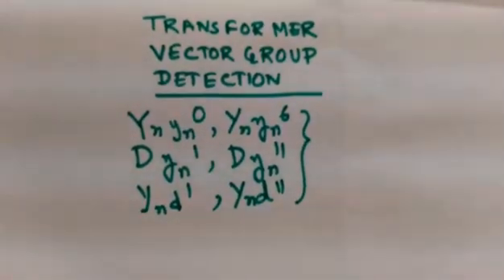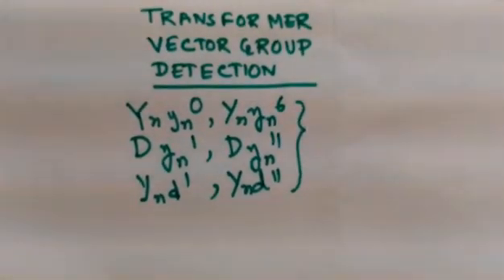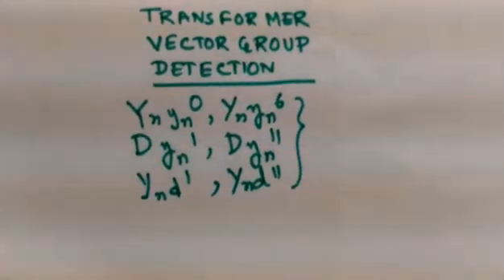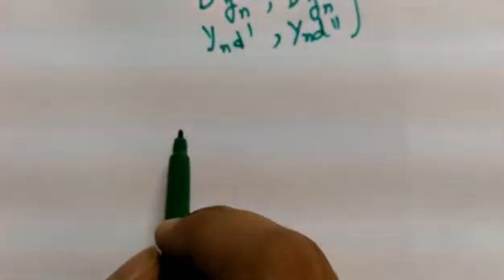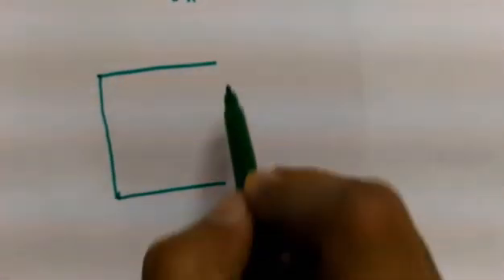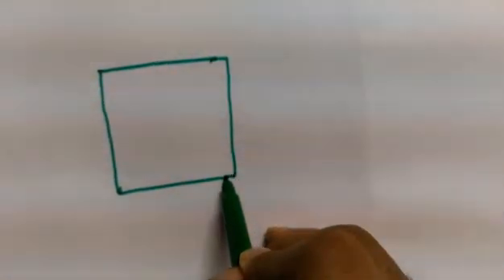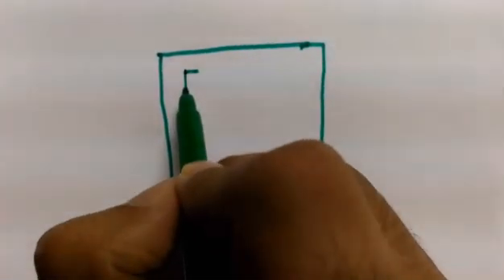Now we will see, after manufacturing of the transformer, how the vector group is identified — whether the actual vector group has been obtained or not. Let us see what the procedures are. We will first discuss about the star-star transformer, that means whether the vector group is YnYn0 or YnYn6. This is my transformer — these are the primary terminals, or the high voltage terminals.